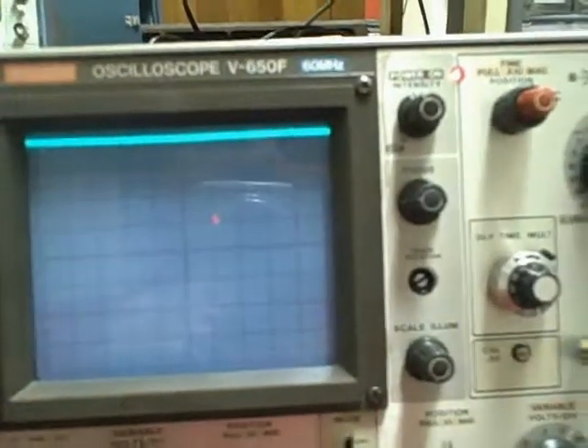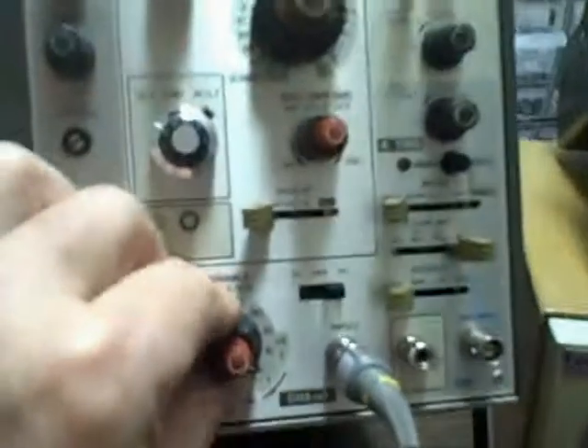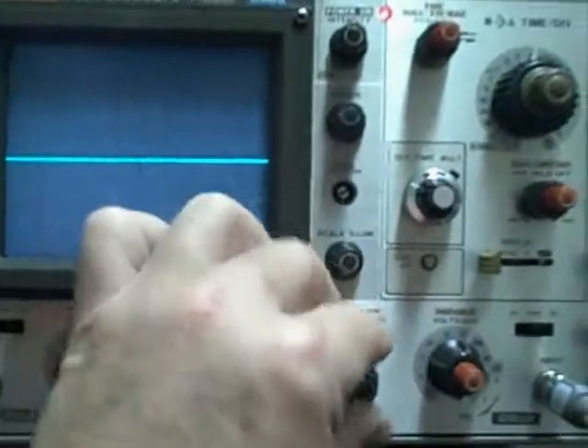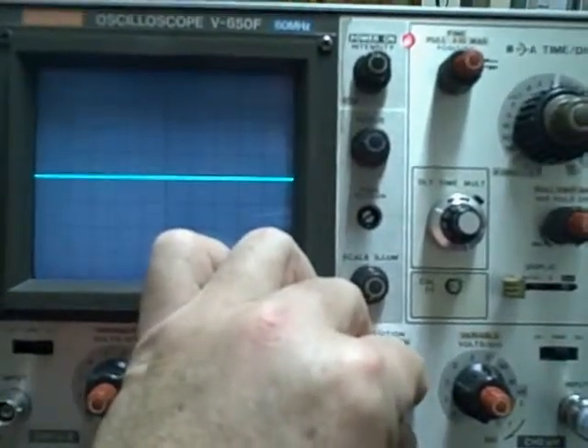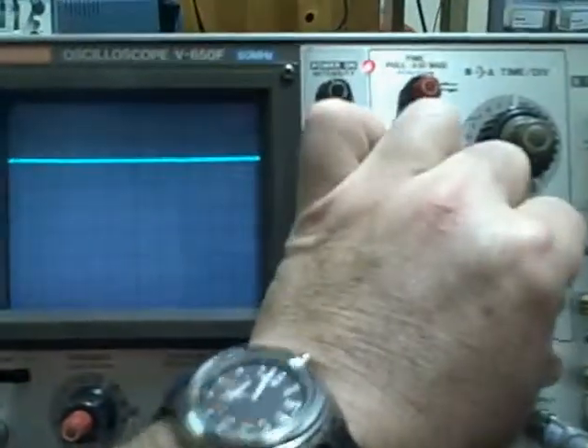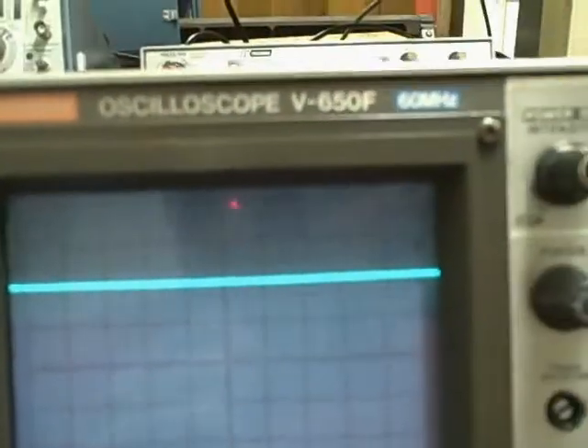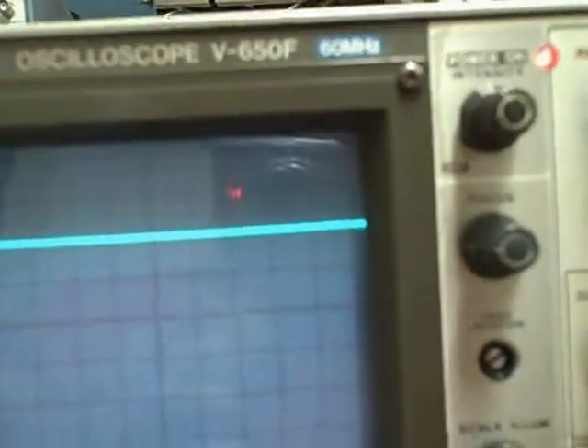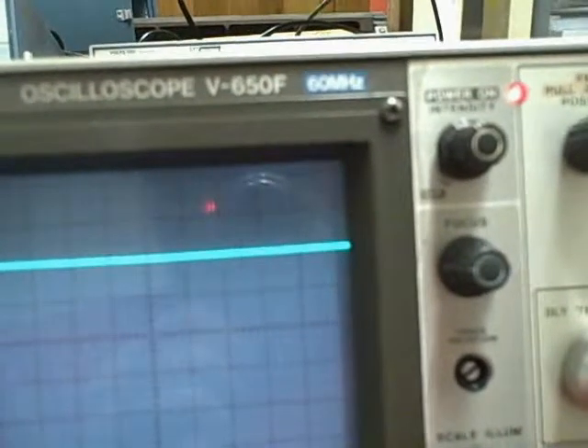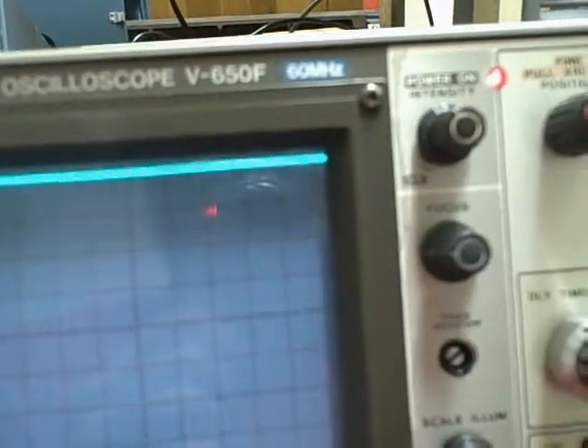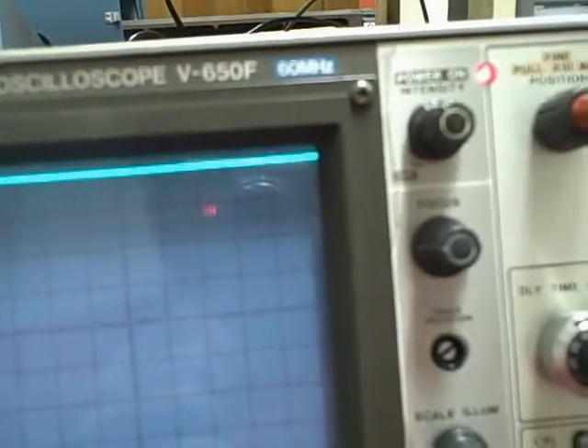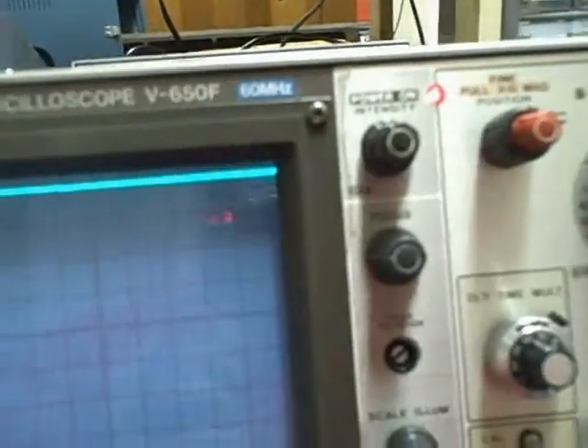Now if I raise my scale to 10 millivolts per division, check my zero, I am 2 divisions up. And I can go ahead and take myself up to 40 millivolts per division. It's a little touchy, that's about 40 there. I'm running 39.3, 40.0 right there, so we are full scale.